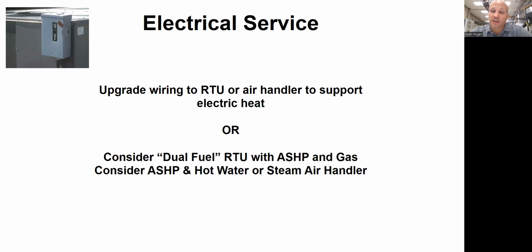But when you have a gas-fired split system, also when you have a packaged rooftop, that's when it becomes unlikely that you're going to do the dual fuel system. And you're probably going to have to pick a lane. Either you're going to go all electric because that's the way your life is headed, or you're going to stick with your gas furnace and not do the heat pump. Not that you couldn't do it, I guess. You could get an outdoor mounted duct furnace, horizontal discharge rooftop unit, and connect it together like a Lego kit, an erector set. But it's probably not the best from an operational and service standpoint.